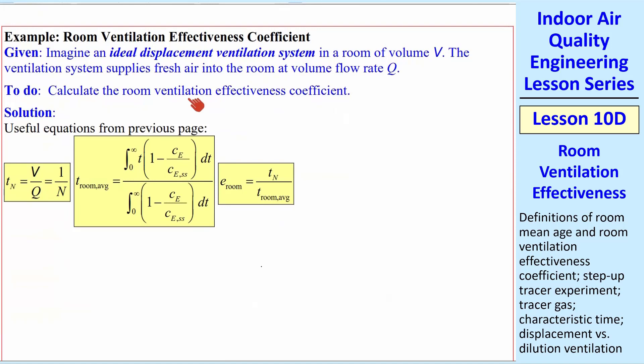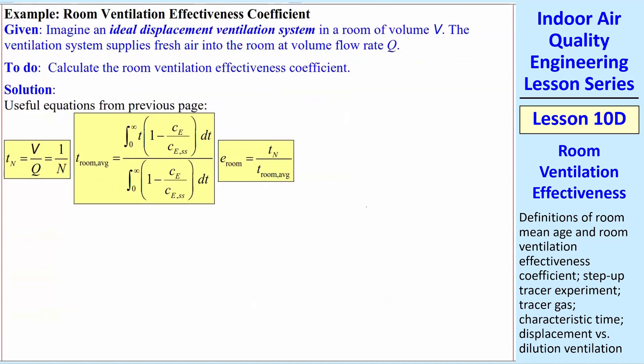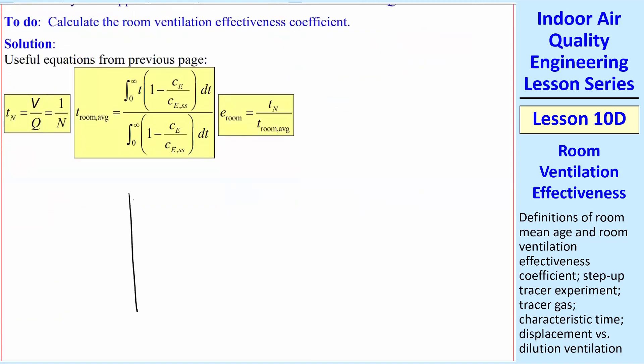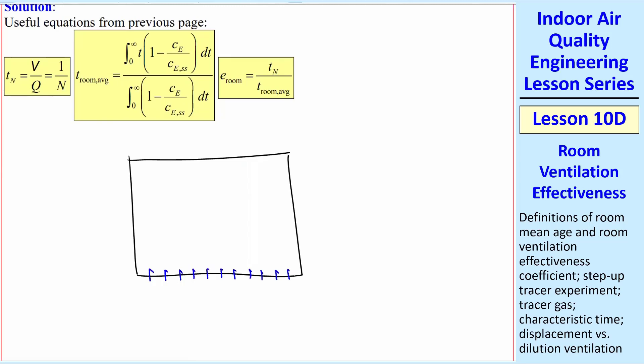Let's do an example. You have ideal displacement ventilation in a room of volume V, volume flow rate Q. Calculate the room ventilation effectiveness coefficient. We're talking about ideal displacement ventilation. So let's review quickly what we mean by that. Best example of that would be if I had a room with evenly distributed tiny holes on the floor where the air is coming in, supply air Q. And then the exhaust would be coming out little holes in the ceiling. And there's no mixing going on at all. So you have at some time T, this region. You'd have C equal constant here. And you have C equal 0 here. So the stale air is actually the clean air.